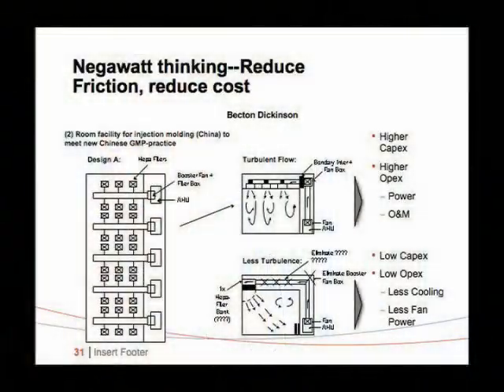And of course, I knew somebody and he brought me in and he said, this is going to add a lot of horsepower. What do we do? So I said, you can actually do this cheaper and better because you are not constrained by rules of thumb that say so many square feet, so many air changes, so many filters. Go back and rethink. We don't want this turbulent flow in an injection molding area, which is making syringes. We need to have a kind of unidirectional flow.